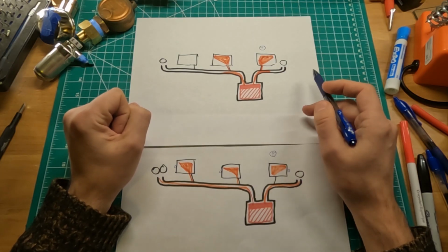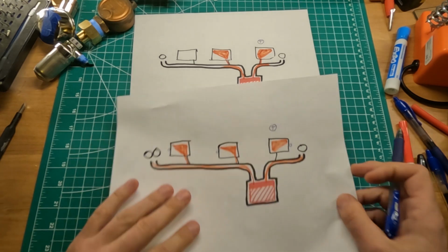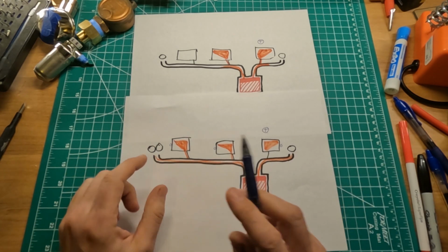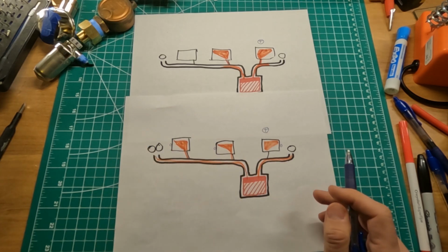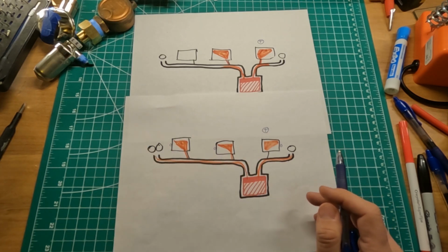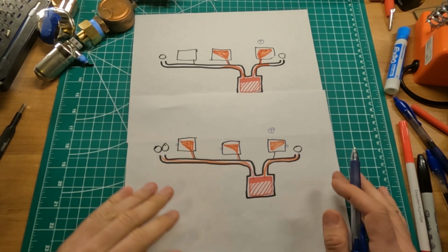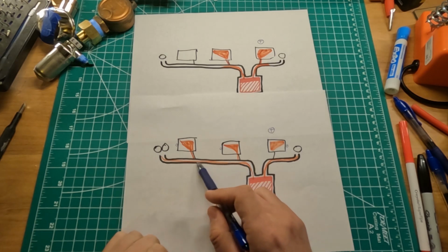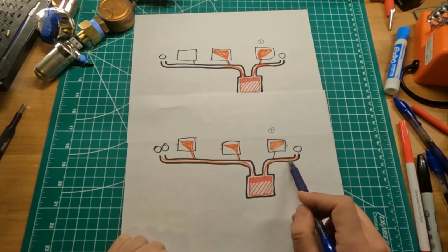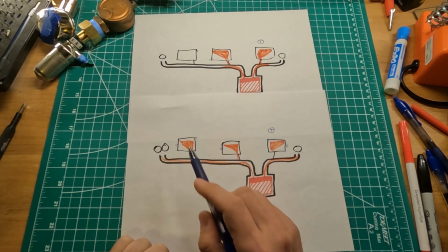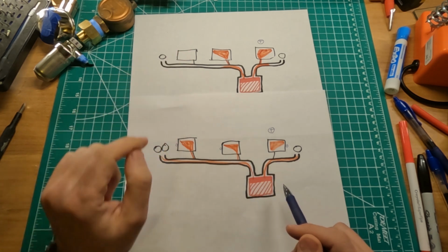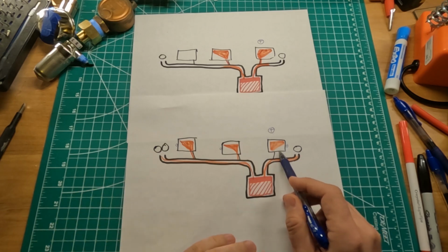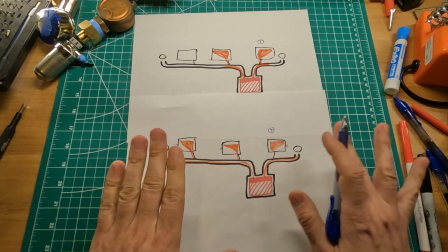And all I ended up doing is going to this scenario where basically I had an extra vent under my long leg, and it already had quite a big vent. I think it has a Gorton number 2, if I remember correctly, and I added one more, and that changes things dramatically. All of a sudden this leg got filled up before this started being even warm, and then all the radiators that before would stay quite cold started getting heat, and then this radiator started getting heat secondary, and that solved my problems of how to balance.